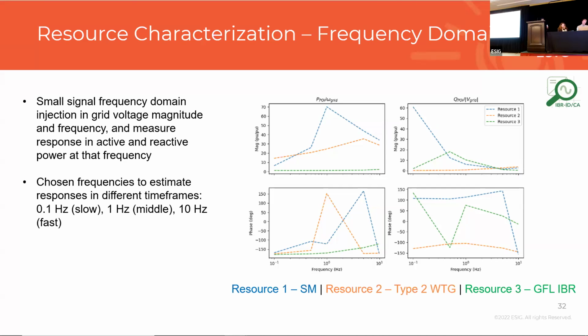We look at how the resource's active power will respond to changes in frequency on the system, and how the resource's reactive power will respond to changes in voltage magnitude on the system. The y-axis will essentially say that if the frequency changes by x per unit, some value, how much will the active power change by? So it's just the ratio of active power change to frequency change and ratio of reactive power change to voltage change. Now, these particular graphs themselves are not a generalization of the behavior. They are particular models that were there in the case that we were looking at.